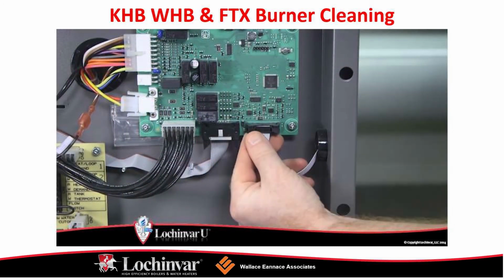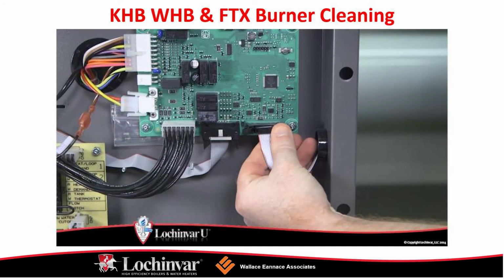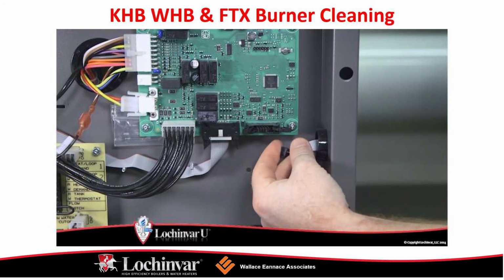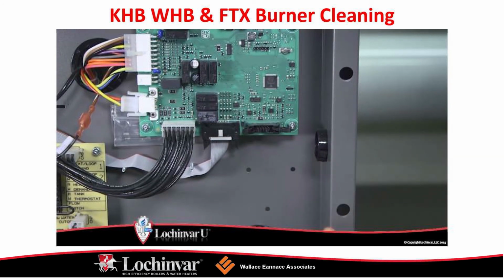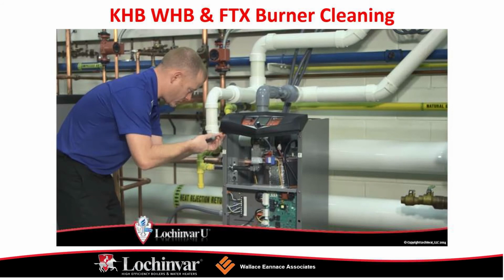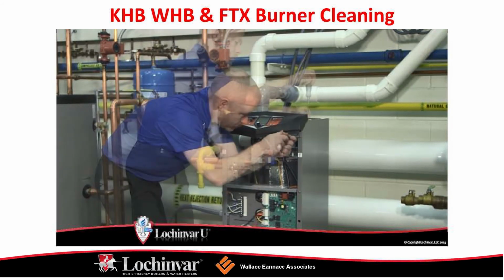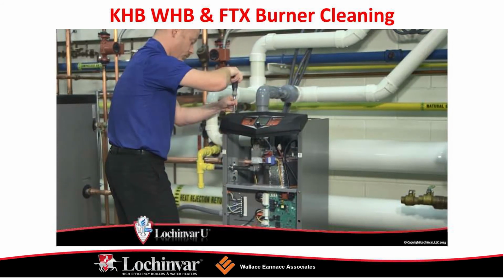Turn the on-off switch to the off position. You can now replace the front panel on the unit. Replace the plug from the vent fitting. Turn the on-off switch to the on position. The unit is now ready to accept the heat demand.